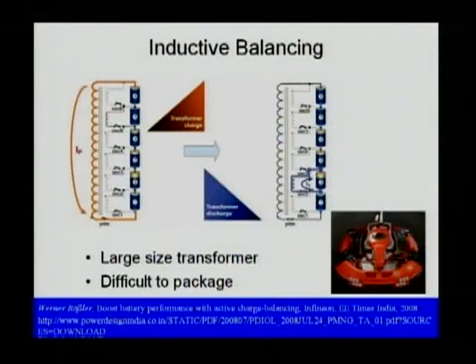People also developed multi-winding transformer balancing, called inductive balancing, for a battery system. The primary of the transformer has one winding connected to the battery string, and the secondary has many windings, each connected to a cell of the battery system. In controlling the system, we switch on the primary side so current builds up on the primary winding. Once the current builds up, we open the primary switch, and meanwhile identify which cell has the lower voltage.